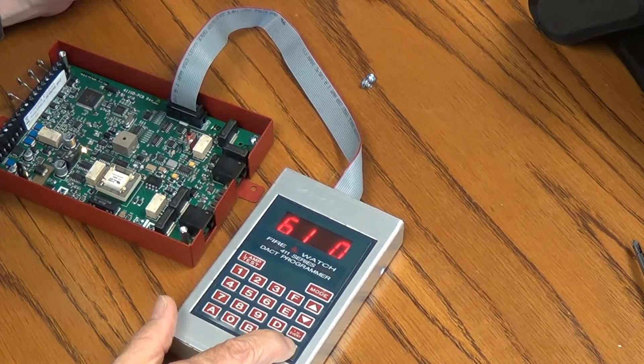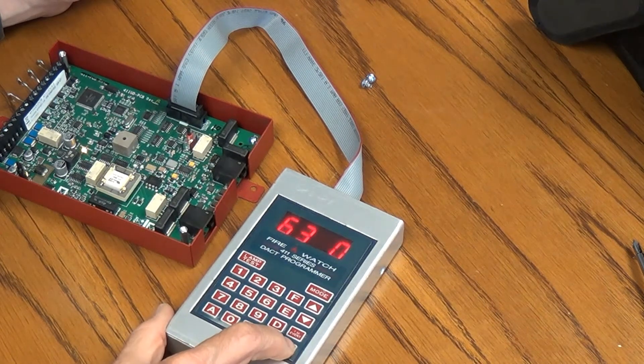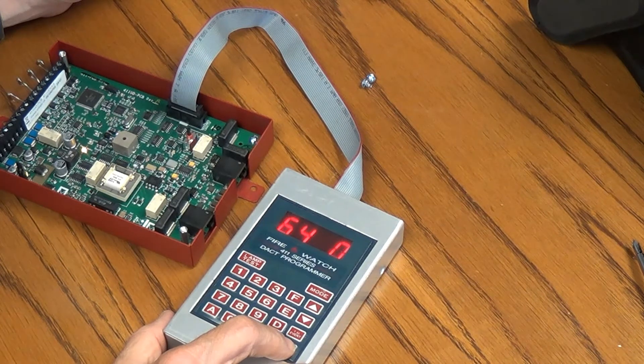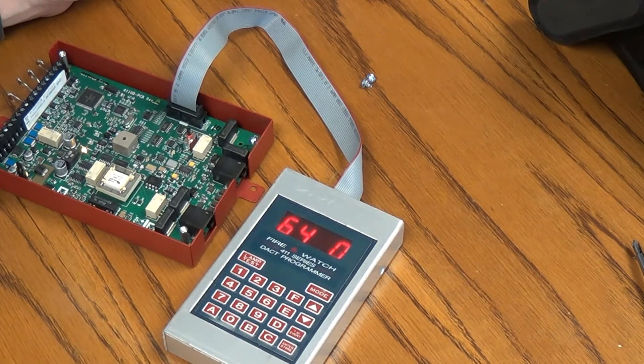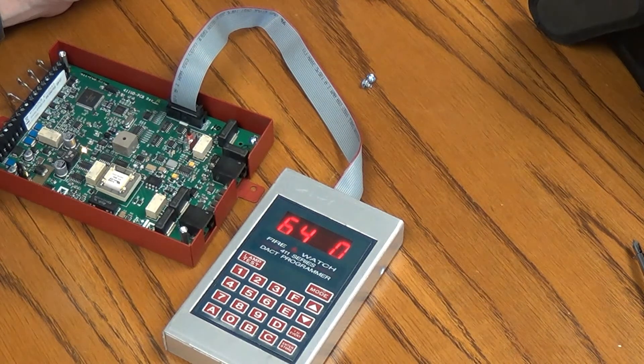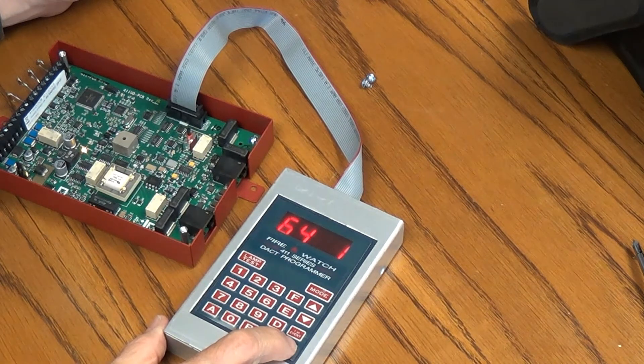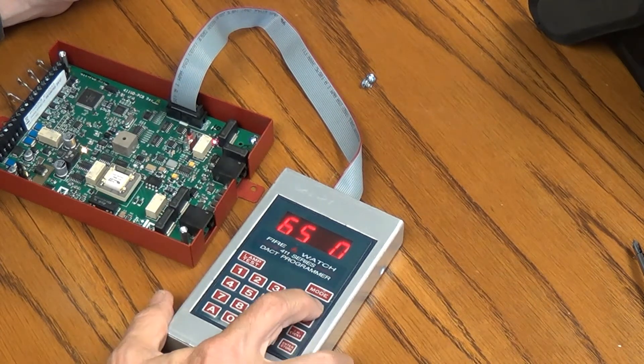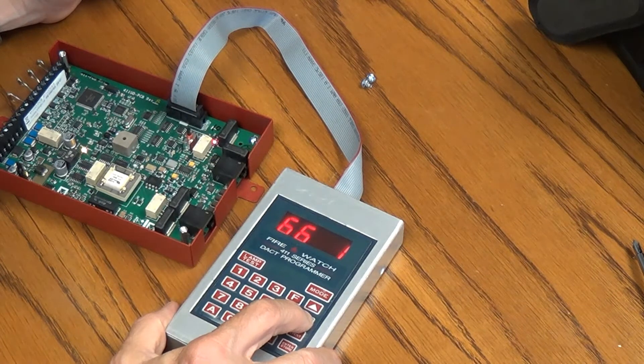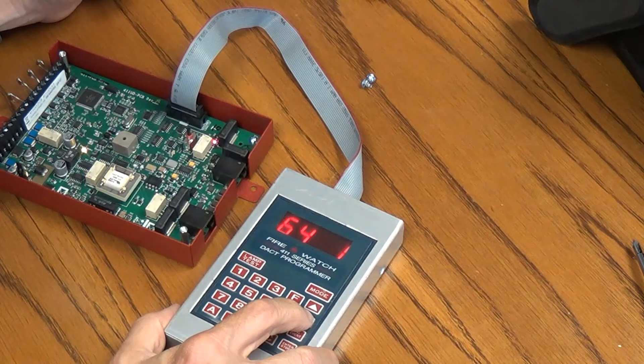We're going to enter until we get to 64. 62 is a 1, that doesn't matter. 63 is 0, that doesn't matter. 64 is communicator enable or disable. Well, we do not want this communicator to be disabled, so we're going to have to put a 1 here. Why it's not default as a 1, I don't know. But 64, important, very important. Let's put a 1 in there. I just heard the relay click on this board, so it knows now that it should be communicating. Again, 64 is 1.